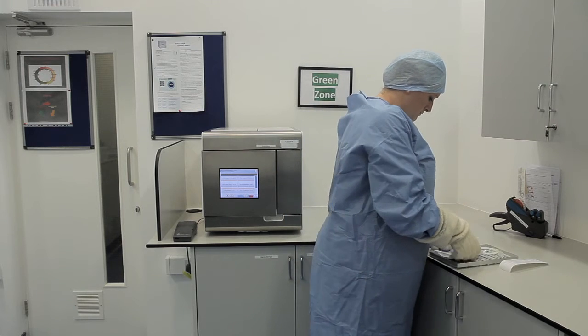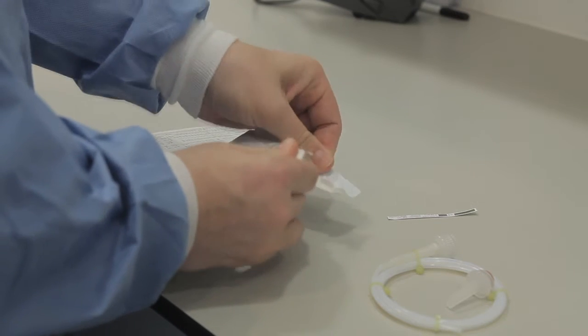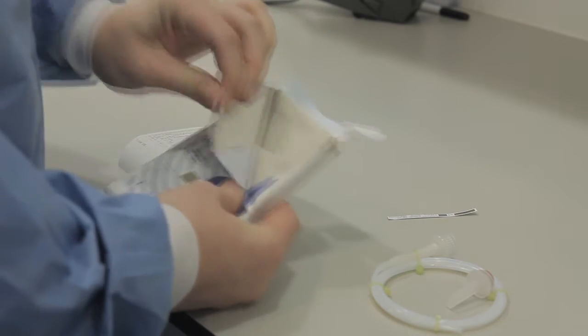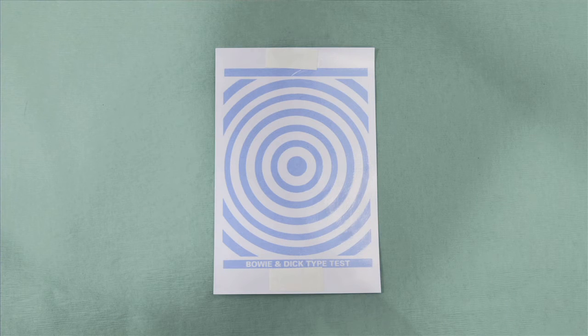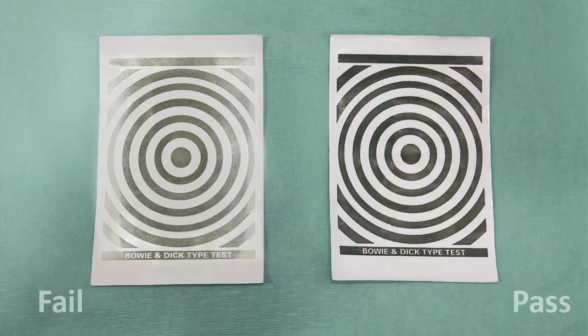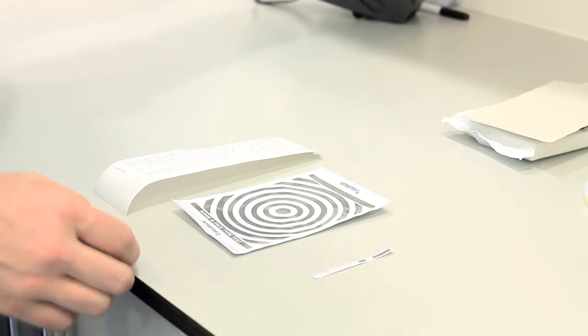Upon completion of the cycle, remove the test pack from the autoclave, open the pack and take out the indicator sheet. The indicator sheet must have changed from a light colour to an even dark colour. If any difference in this colour is noted, repeat the test. Failure may indicate inadequate air or water supply. Review and correct before repeating the Bowie and Dick test. If the second test also fails, it should be recorded as a fail on the indicator sheet, the autoclave log page, and the graph printout should be signed and documented. Do not proceed to the next cycle until a Bowie and Dick test has passed and the graph printout has been signed.